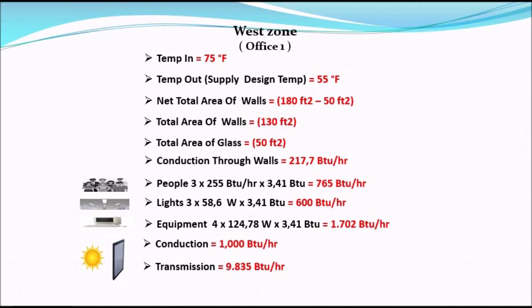West zone office number one has a total area of 180 square feet, minus 50 square feet for the glass area, giving 130 square feet of wall area and 50 square feet of glass area. The total wall conduction is 217.7 BTU/hr, three people working is equivalent to 765 BTU/hr, equipment is equivalent to 1702 BTU/hr, glass conduction load is 1000 BTU/hr, and the glass transmission load is 9835 BTU/hr.